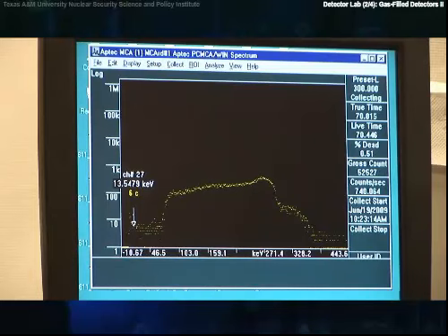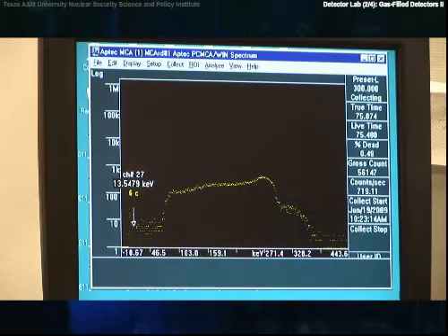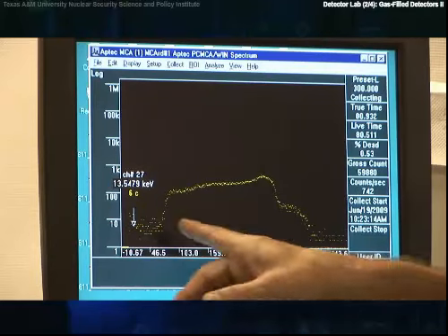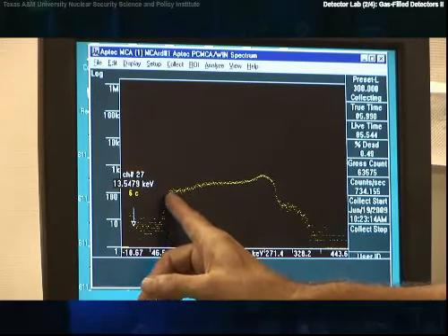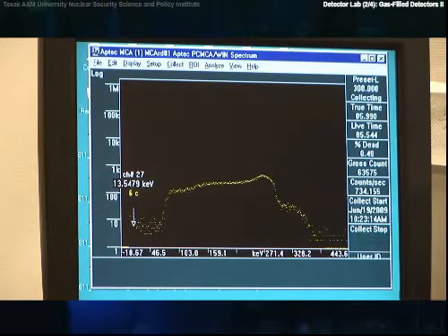But this spectrum will continue to grow in, and finally the Poisson distributions will get small. But this is not a bad tube to use for neutron detectors. I could set a lower level discriminator here, the gammas would be here, these counts would be neutrons.